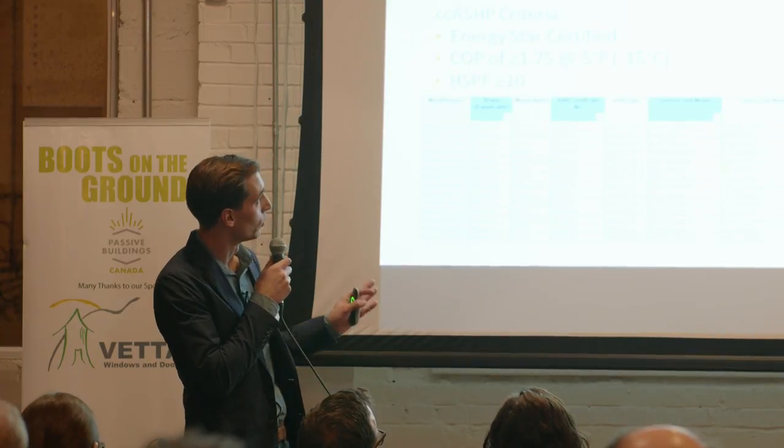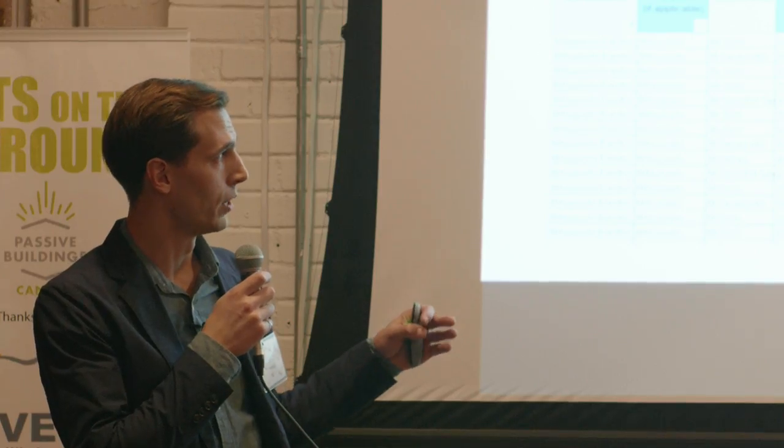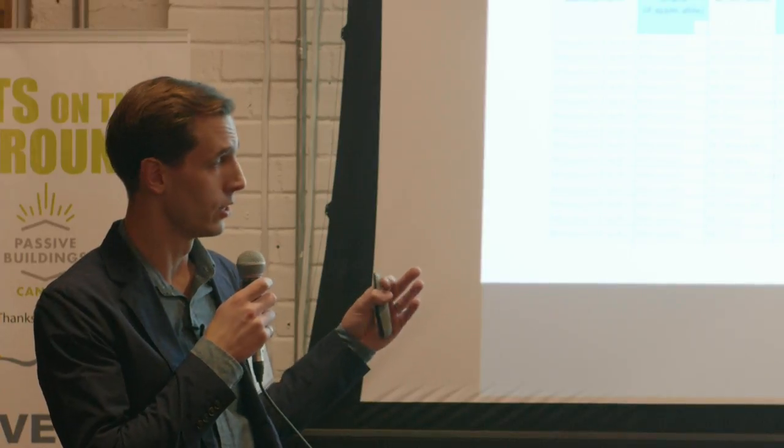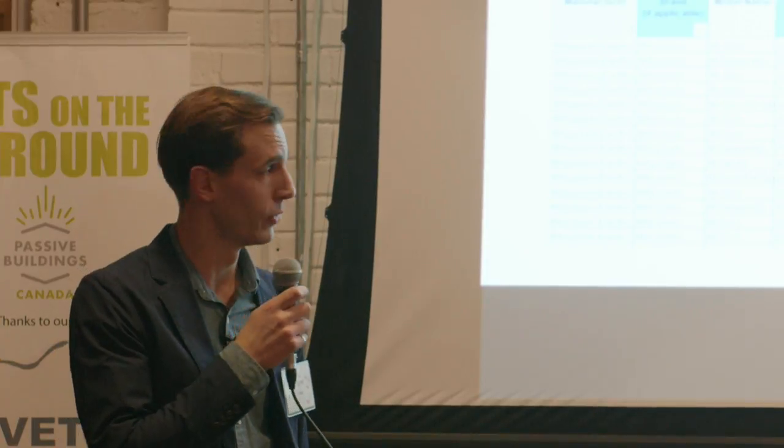I'll leave with one last resource: neep.org, or the Northeast Energy Efficiency Partnership. If you're not already aware of this website, they have a database of cold climate air source heat pumps where manufacturers submit their data and must meet three criteria: Energy Star certified, COP of at least 1.75 at minus 15, and HSPF of 10. If we're designing a heat pump in Ontario to handle all of the heating load, this list is a good place to start to find units that qualify.